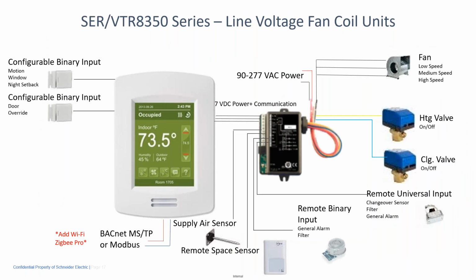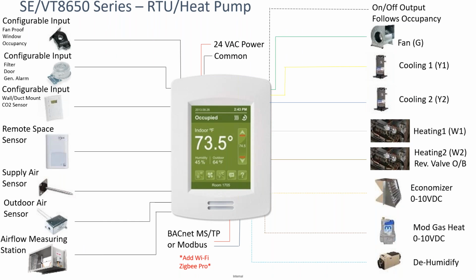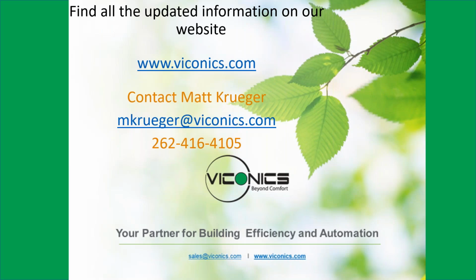Same thing for the line voltage type device, right? So you can have a relay pack there. That's where you bring in the line voltage, and then from that you wire to power the controller on the wall. Configurable binary inputs connect to it, and then the supply air sensor, remote sensor, and outputs to your heating and cooling valve are there. And we'll do one more here, just a rooftop unit. Again, configurable inputs, remote space sensor, supply air sensor, outdoor air sensor, an input for airflow measuring station. You can have modulating gas heat, stage heat, cooling stage, fan, and then an output that follows occupancy. If it's occupied, it's open or closed, and you configure it that way. And again, any of these types of configurations can be modified with any sort of Lua programming that would be required to do unique situations.